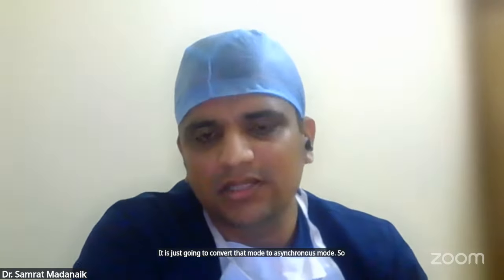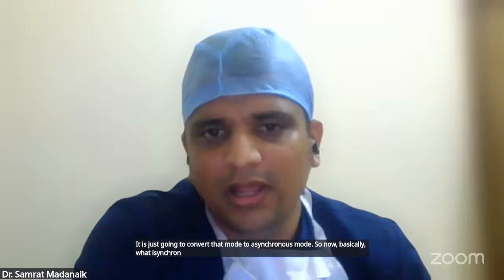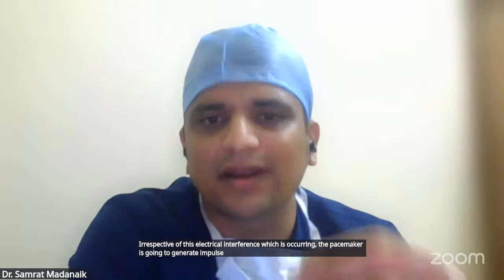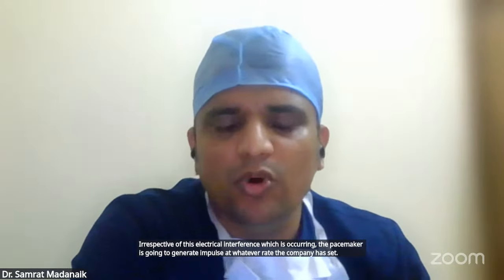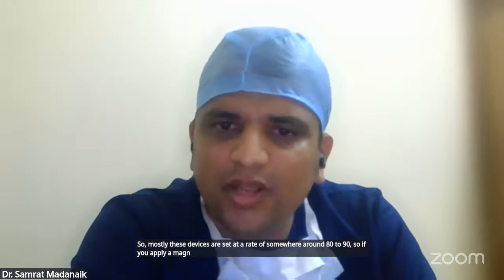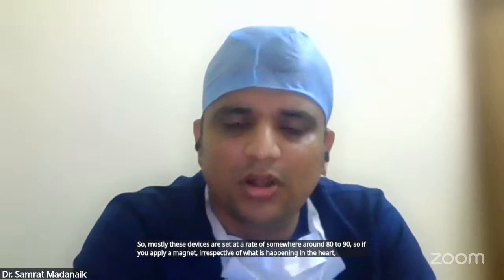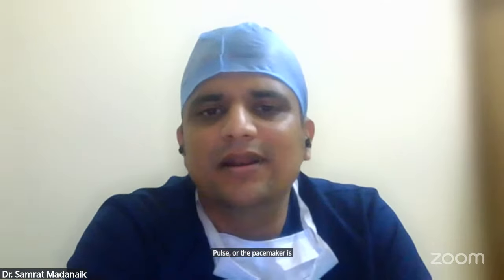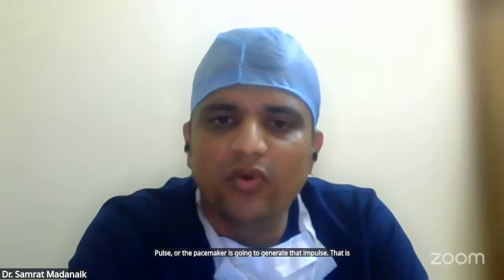So now, what is asynchronous mode? Irrespective of the electrical interference which is occurring, the pacemaker is going to generate impulses at whatever rate the company has set. Mostly these devices are set at a rate somewhere around 80 to 90. So if you apply a magnet, irrespective of what is happening in the heart, the pacemaker is going to generate that impulse. That is, it converts the pacemaker into asynchronous mode.